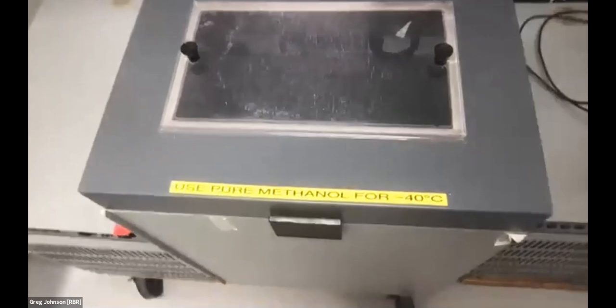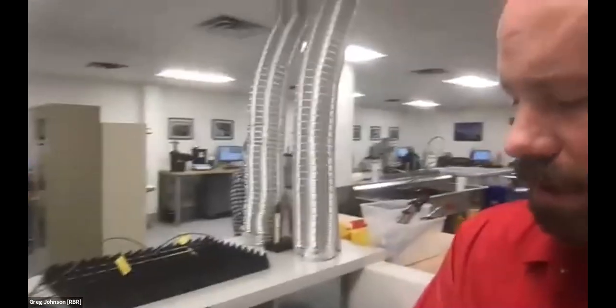That's water mixed with methanol in there. And that's because we calibrate from -5 to 35 degrees Celsius, and we don't want that fresh water to freeze. In fact, we have a bath that we also will take down to -40 when we're doing extended calibration. So although our standard range is -5 to 35, we'll do extended temperature calibrations up to about +50, down to -40, and those differ according to your requirements. We wouldn't typically recommend that battery-powered instruments go to more than +50. The batteries don't like it very much.